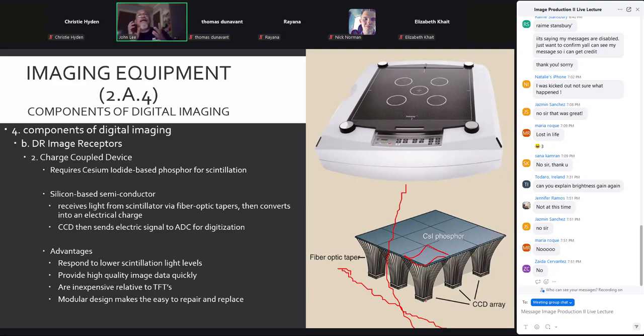Again, our advantages for these things, they respond to low scintillation levels. As you can see in the diagram there, we do have a scintillator, the cesium iodide, converting X-rays to light, and then the light being tapered down by the fiber optics to the CCD. The CCD, comprised of silicone, has TFTs in it, has storage capacitors in it. It's basically a mini flat panel, but a mini indirect capture flat panel. So it requires scintillation, conversion of X-rays to light, and then light to our electric signal. Because it is modular, any one of these goes out, it's easy to replace, very inexpensive compared to our flat panels themselves.